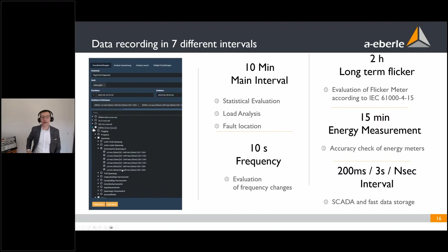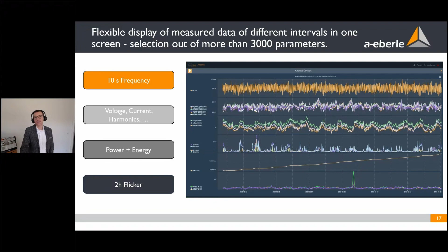Here an example of our software WebPQ, where we have the opportunity to display all these data afterwards. Here 10-second frequency, voltage, current, harmonics, power, and energy in the 2-hour flicker value, for example. And this can be done out of 3,000 parameters. It's up to you which parameters you want to record on the device. One good thing is I explained that like that there is no fault recorder inside the device in the first solution, so in the cheapest solution, but you can extend this fault recording if you want to.